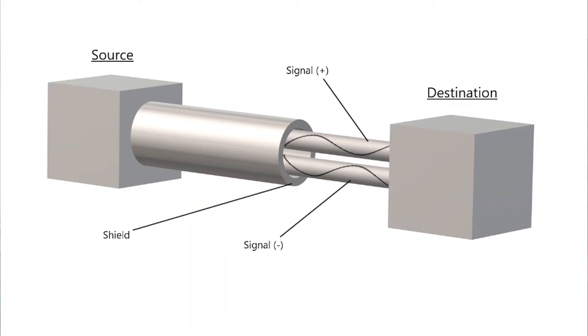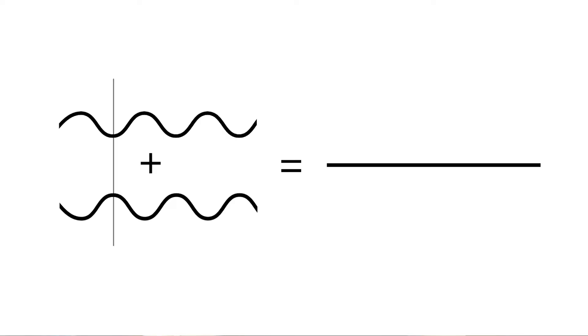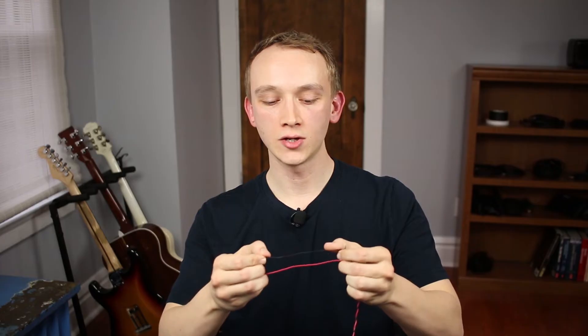How does twisting the wires of a circuit help protect the signal on that circuit from noise? Remember that any circuit is made up of two wires each with opposite energy. So if there's a positive voltage on the black wire there will be a negative voltage on the red wire and vice versa. The polarity of the electrical current through each wire is opposite, and the polarity of the magnetic field around each wire is also opposite. When opposite forces are added together they completely cancel out.